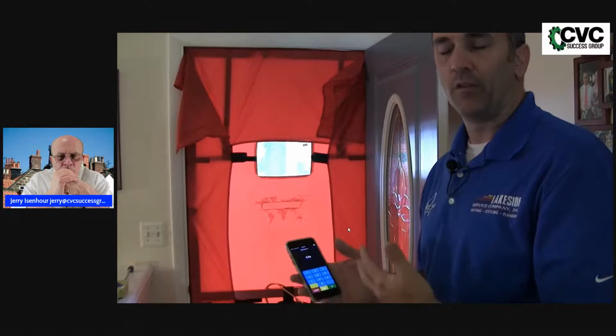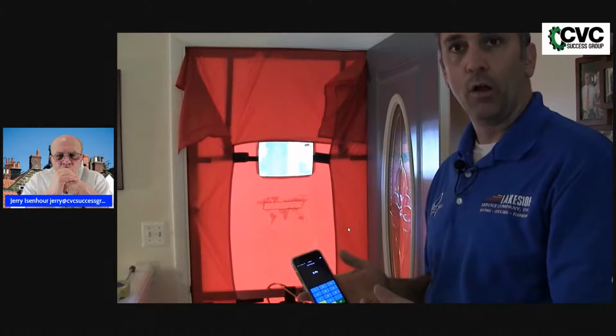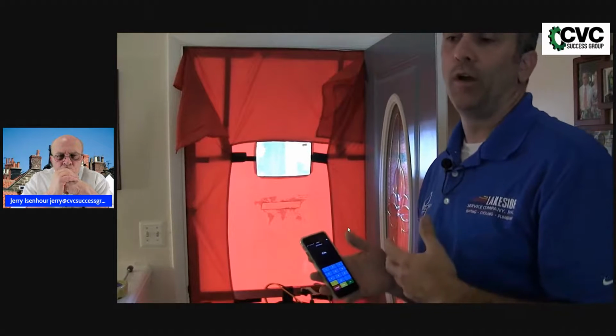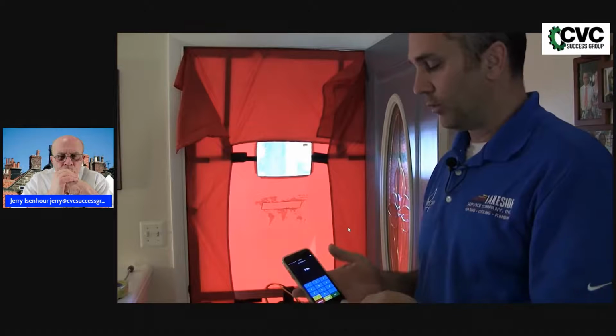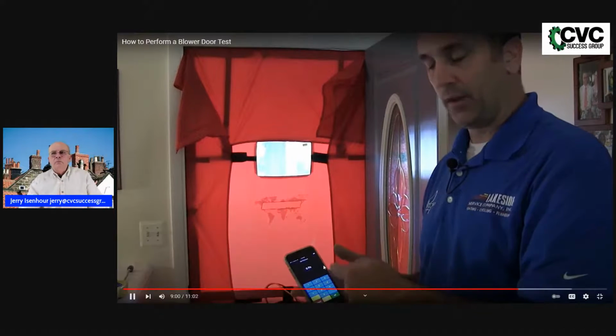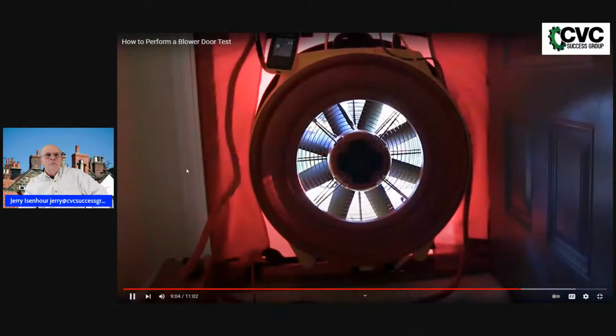At 25 Pascal, it's about half speed. So that's, again, another safety protocol, that we just don't fire up the blower door and run it, because what if I'm going to cause damage or harm to that person's home? So I'll set it at 25 Pascal just as an illustration, 25, and I hit set. Set pressure, 25 Pascal, go.